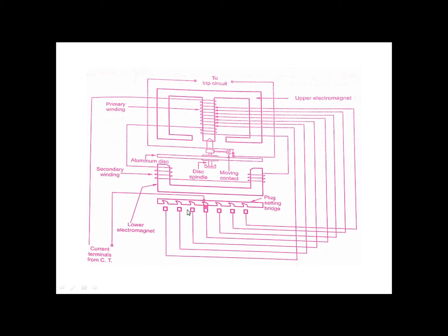The secondary winding on the center limb of the upper E-shaped magnet is connected in series with the winding on the lower U-shaped magnet. This winding is energized by induction from the primary. By this arrangement of the secondary winding, the leakage flux of the upper and lower magnets are sufficiently displaced in space and time to produce a rotational torque on the aluminum disc. The control torque is provided by the spiral spring.